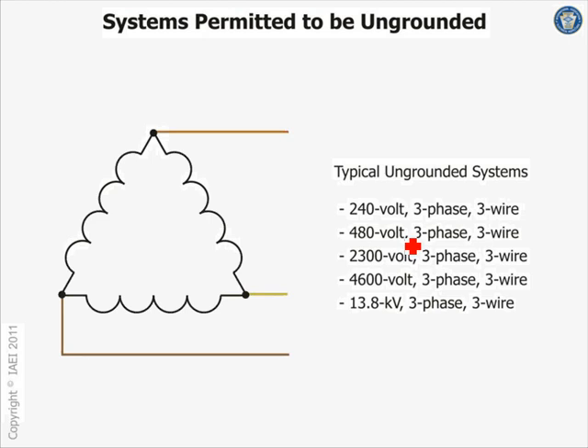Anybody dealt with 208 ungrounded? 208, it's coming from a Y. The reason for a 208 coming from Y. A 480 could be coming from a Y or a delta, right? 480 can come in from a Y or delta. 240 is coming typically from a delta, but it also can be coming from a center tap delta. But a delta like this will give you 240 or 480.